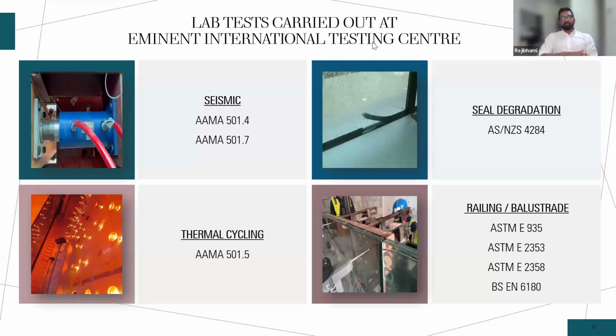The normal temperature, for example, is 22 to 24 degrees Celsius. We increase the temperature up to 80 degrees within 1 hour, then maintain that 80-degree temperature for 2 hours. Then it's brought back to normal temperature within 1 hour. Then the temperature goes down to minus 18 degrees Celsius, maintained for another 2 hours, then brought back to the normal temperature of 22 to 24 degrees Celsius. This is called one thermal cycle.